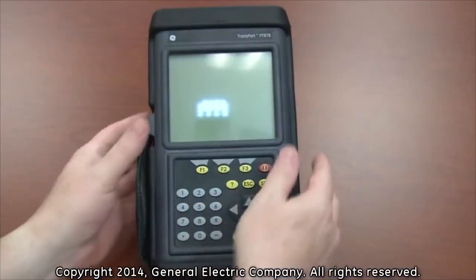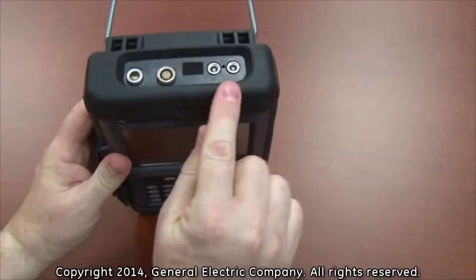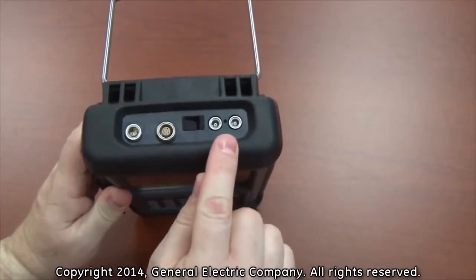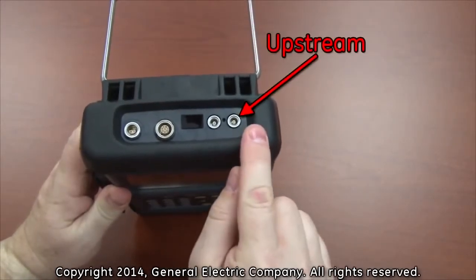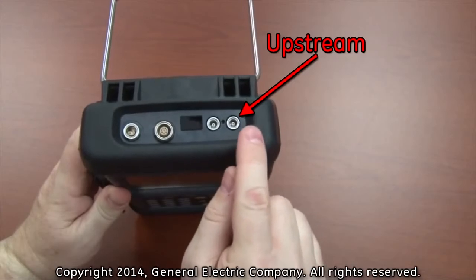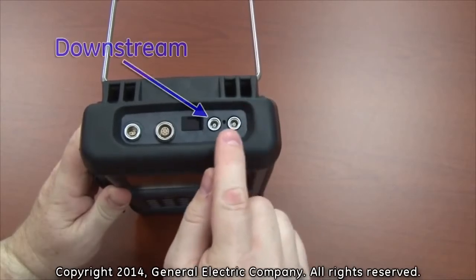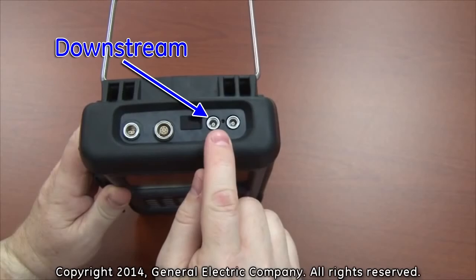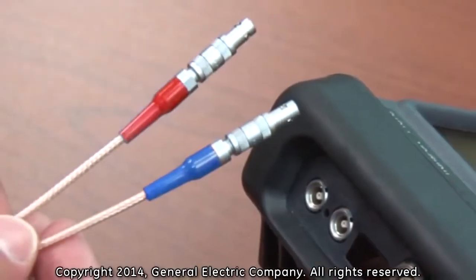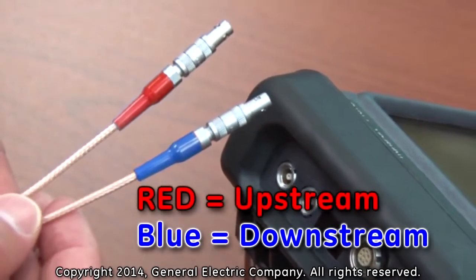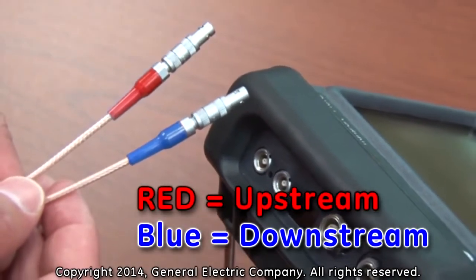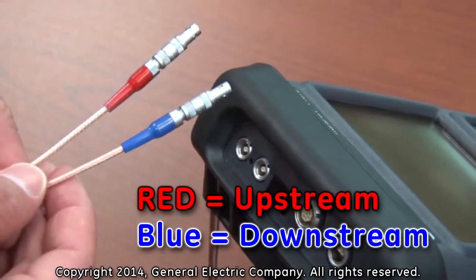The transducer cable connections on the PT878 are located on the top right-hand side of the device. The upstream connection is the port closest to the right-hand edge of the device. The downstream connection is located next to the wireless infrared communications port. The upstream and downstream cable connections are identified by color code, red for upstream and blue for downstream.